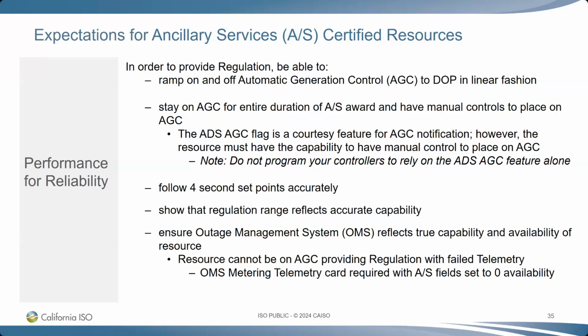The ADS AGC flag is a courtesy feature for the AGC notification, but the resource must have the manual control capability to be able to place on AGC. You need to be able to follow the set points accurately every 4 seconds, and show that the regulation range reflects the accurate capability.